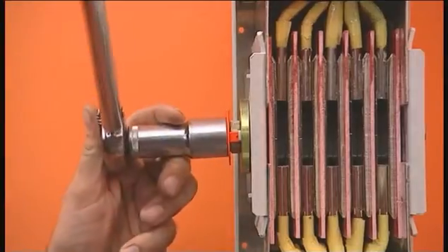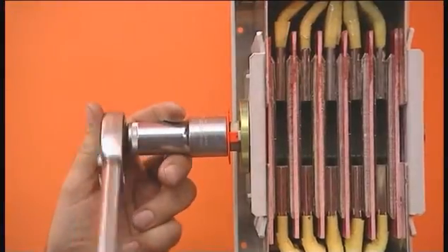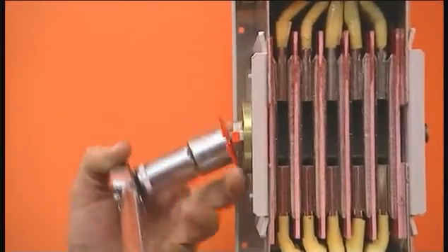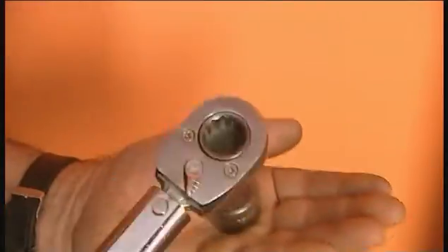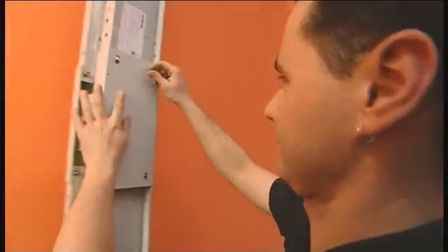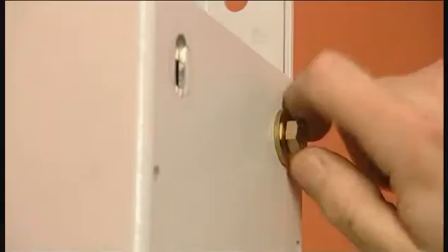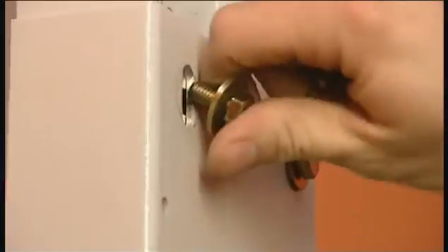When first installing the single bolt clamp, it can be tightened without a torque wrench. The outer section of the double head stud is sheared off, corresponding to a tightening torque of 120 newton meters. The maintenance-free bus bar trunking connection is completed by mounting the flange cover.